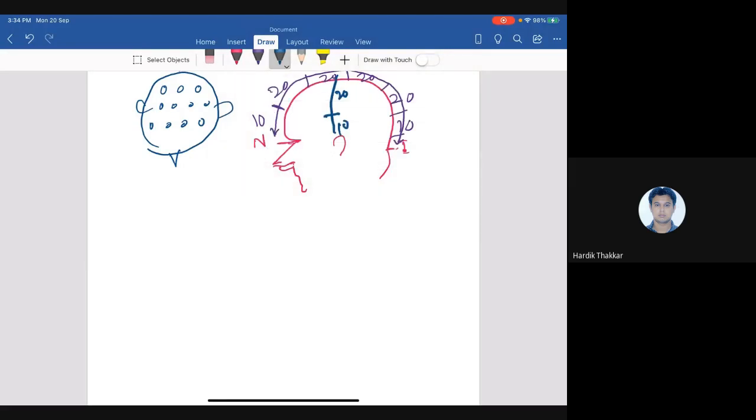After that, you have to rotate in this way, because your head is a sphere. So you rotate this way or that way. From the ear it will go towards the eye, and then again to the other ear. This is again 100%, and the other way also 100%. So again 10, 20, 20, 10, then 10, 20, 20, 10. This is called the 10-20 electrode placement system.